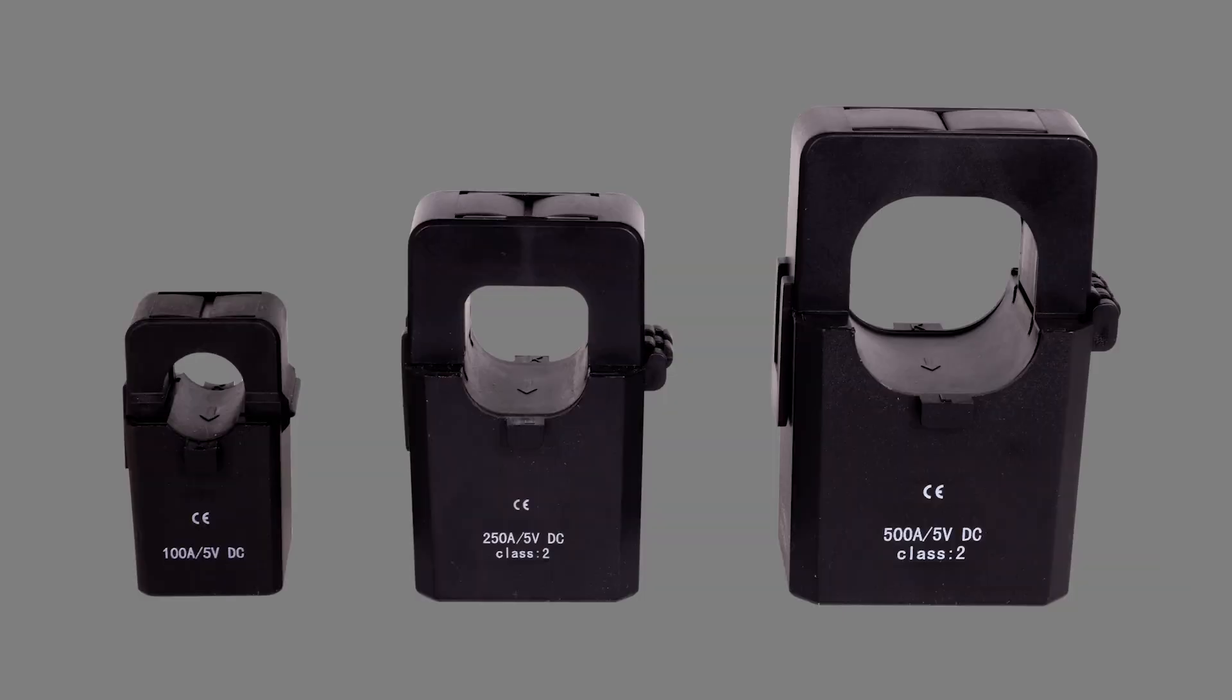It comes standard with 250-amp, 5-volt CTs, but 100 and 500-amp CTs are available upon request. The ampacity of the CTs is stamped directly on the CTs and should be verified before programming.